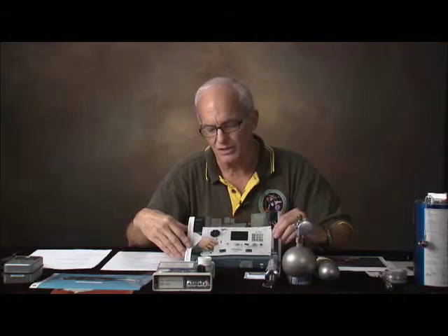So minimize crew time. Another thing to minimize is how dependent your devices are on the resources of the parent vehicle. For example, the volatile organic analyzer was dependent on nitrogen from one of the ECLSS systems to operate. We were not aware that ECLSS was going to periodically shut down the nitrogen system to purge it, and they didn't know to tell us. So we had some real hiccups a few times when they were maintaining their nitrogen system, and our instrument went crazy wondering what happened to its nitrogen supply.